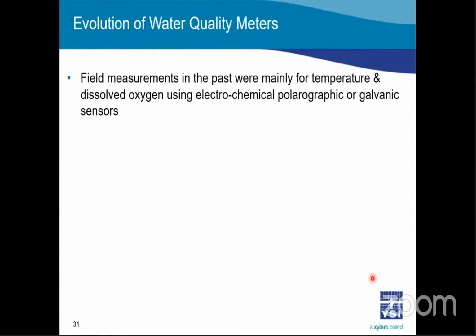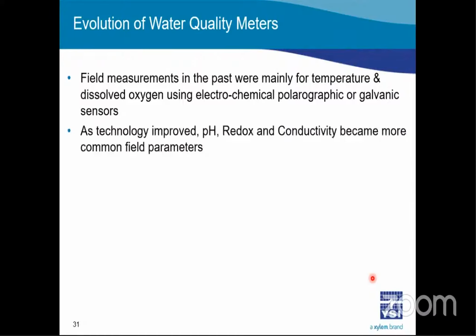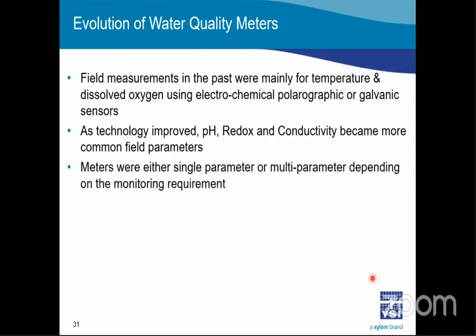They are used in field measurements. In the past, they were mainly for temperature and DO, using electrochemical, polarographic, or galvanic sensors. As technology improved, pH, ORP, and conductivity became more common field parameters that we could measure at the same time. Back then, the meters were either single or multiparameter, depending on the requirement.